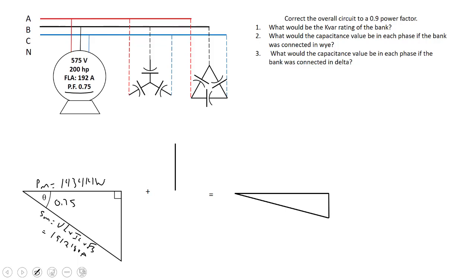Now I can figure out the vertical component of my triangle or the lagging VARs that the motor requires to operate. If I use Pythagorean theorem or if I convert that 0.75 over to angle and use sine times my apparent power, that'll work too. Either way you should get around 126,478 VAR.